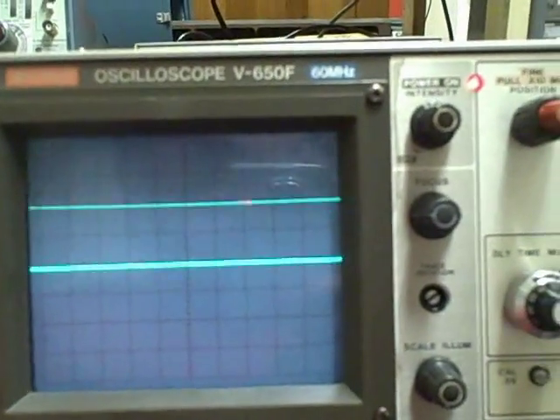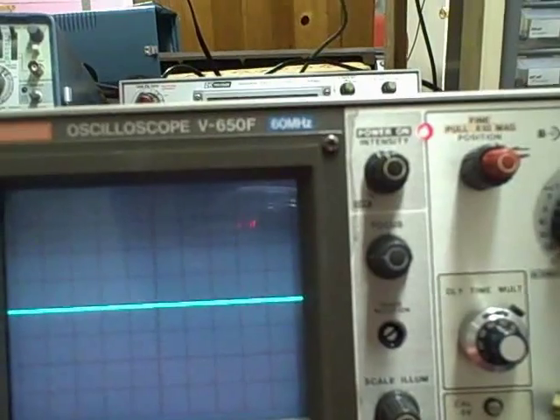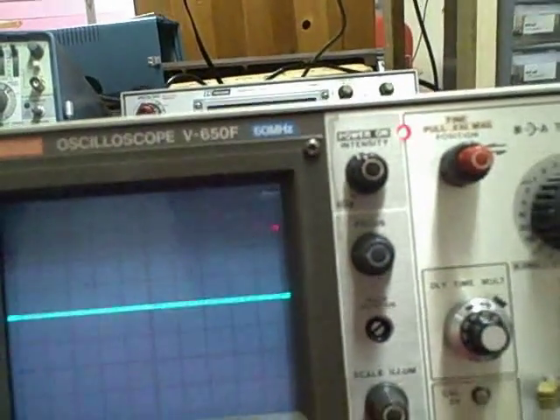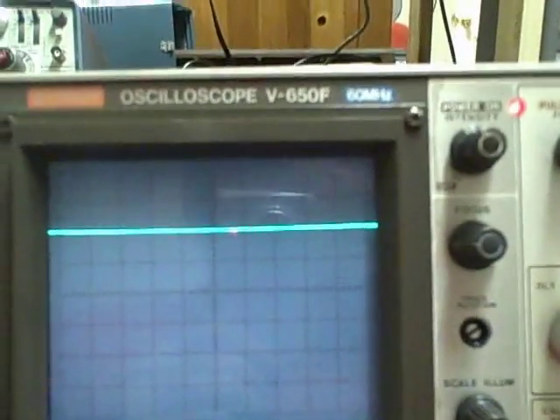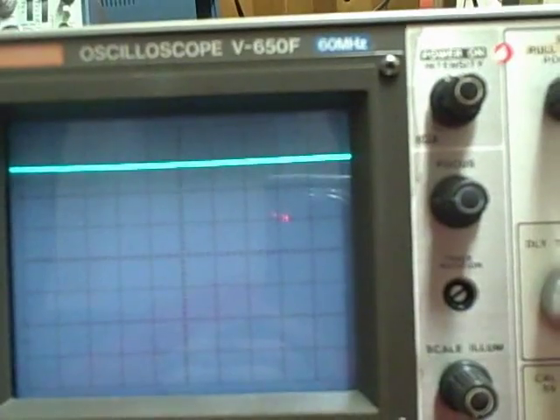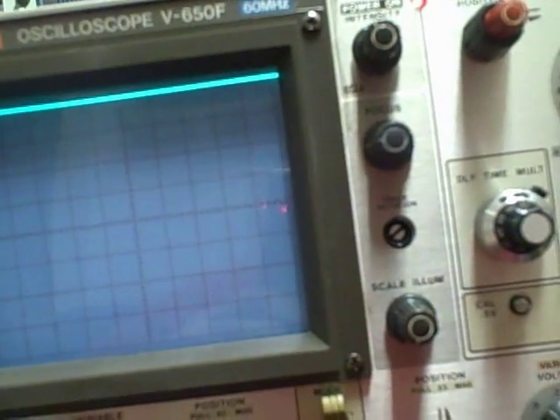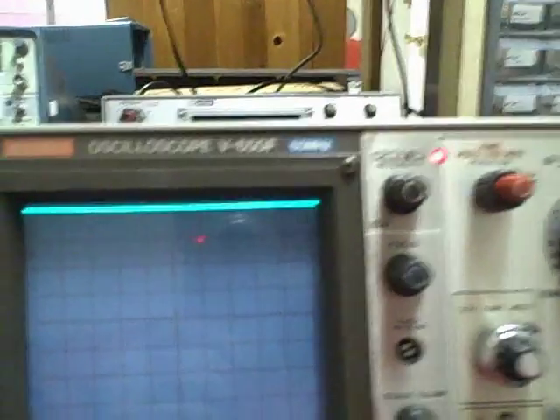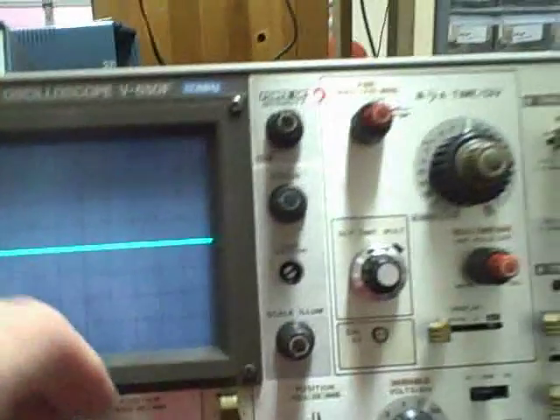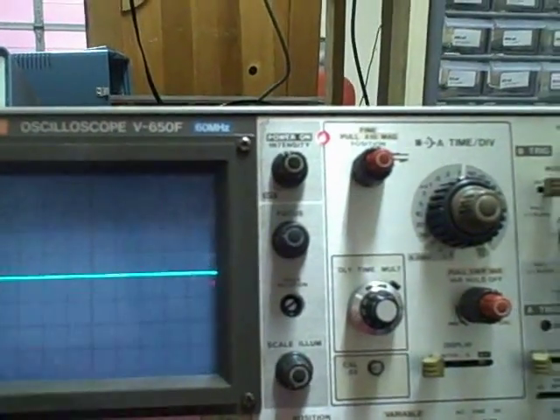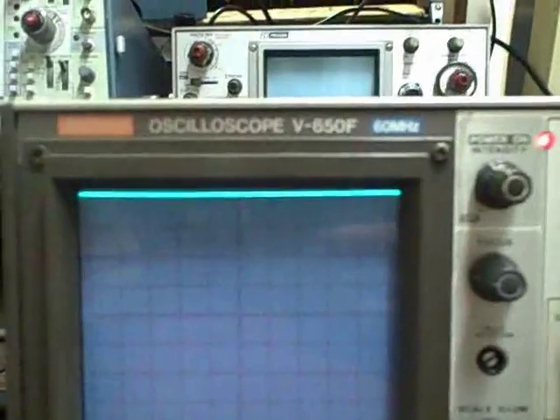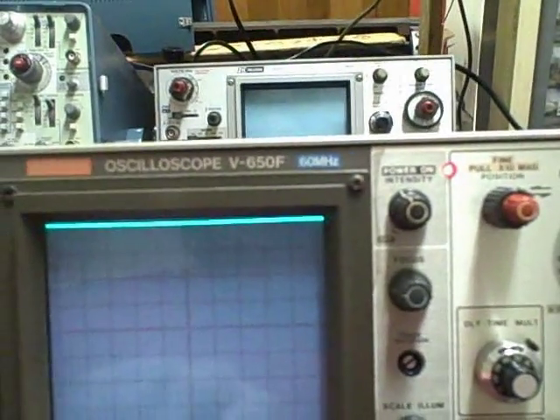Let's go to 0.2 volts per division. And we are on division two at 400 millivolts, which would be right. Let's bring ourselves up. Check our zero. Zero is there. Check our full scale. Full scale is there, and we would be running at 0.2, that's 800 millivolts, and we are running right now 796. So we are within four millivolts of full scale. It's accurate.